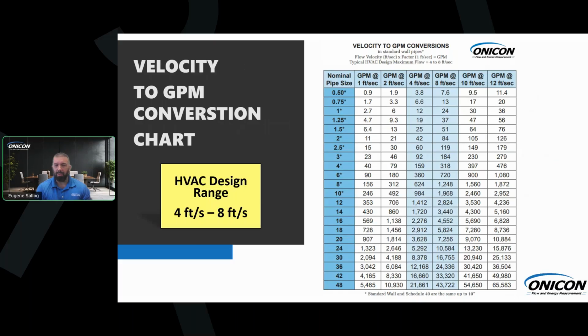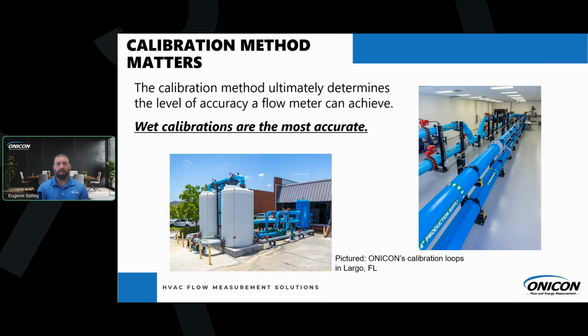If you look at this velocity table, which is very handy, we're typically flowing in the HVAC industry around that 4 to 8 feet per second, which is the sweet spot for heat transfer as far as water flow goes. As you get too fast, it's going to cause too much noise, and not enough heat transfer is going to take place, and it's going to be inefficient. So we're actually operating at the lower end capability of a flow meter, especially this one, right? This one tops out at 33 feet per second, but we're seeing mostly that lower end. So the accuracy statement is very critical when we're looking at it this way. That's why all of our meters are wet calibrated. We need to put them in the pipe, flow the water through it that they're going to see in the real world around that 4 to 8 feet per second, and fine-tune the accuracy to make sure that we are reading correctly.